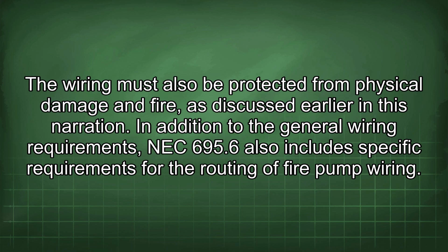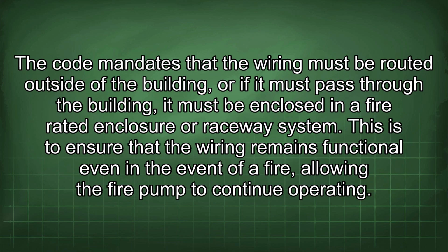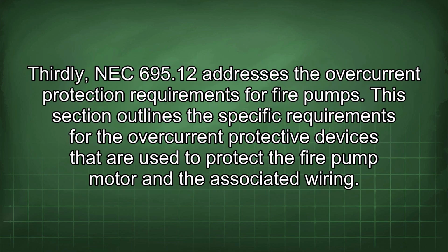695.6 also includes specific requirements for the routing of fire pump wiring. The code mandates that the wiring must be routed outside of the building, or if it must pass through the building, it must be enclosed in a fire-rated enclosure or raceway system. This is to ensure that the wiring remains functional even in the event of a fire, allowing the fire pump to continue operating.